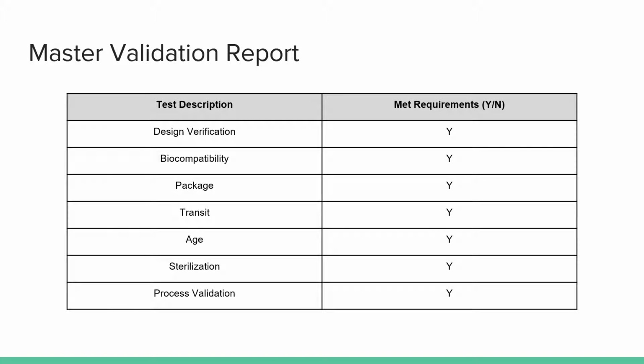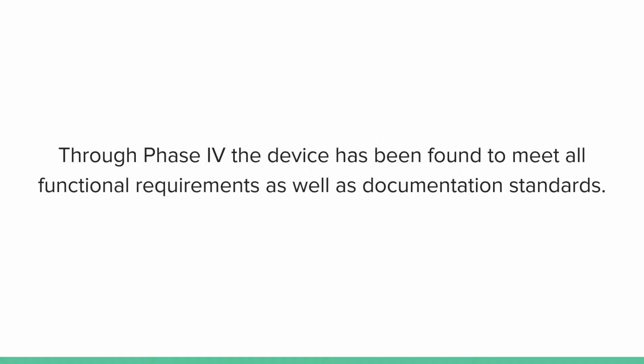So the master validation report is to ensure that all equipment and processes for the device have been properly documented and validated. Each of the following tests had to meet the accepted results, or else there will have to be revalidation of that particular step. Since all the required testing have met all the criteria, the implant port can be commercialized to the open market. With all of this in mind, it has been found that through Phase 4, the device has met all of the functional requirements as well as the documentation standards.